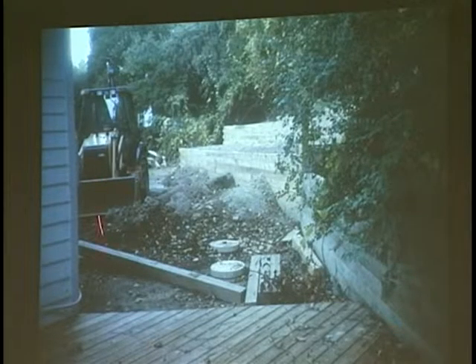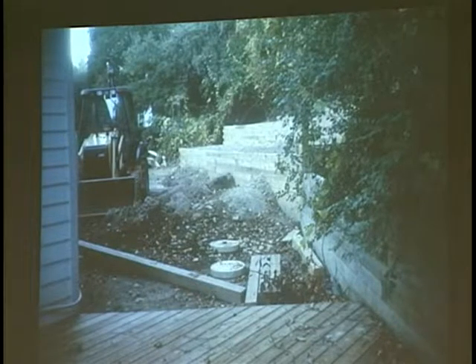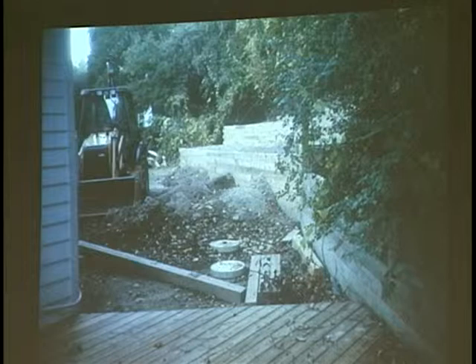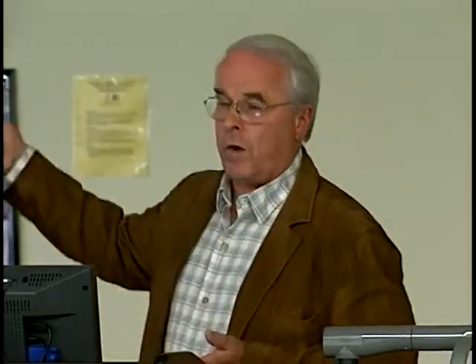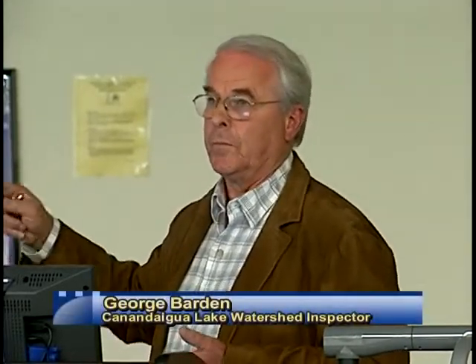Similar situation on this one — rusted-out steel septic tank underneath this deck caved in. This gentleman had one leach line in the driveway area that was, number one, less than 100 feet from the lake, and number two, it was below the 10-year flood elevation of the lake. Appendix 75A says leach systems are unacceptable below the 10-year flood elevation. The 10-year flood elevation of Canandaigua Lake is 690. Appendix 75A doesn't say how far above the 10-year flood elevation you're supposed to be, so we adopted one foot — meaning the bottom of any leach trench needs to be at elevation 691. At least once every 10 years when we have a high water condition, the leach line is at least out of the lake water by one foot. That's what we've adopted.